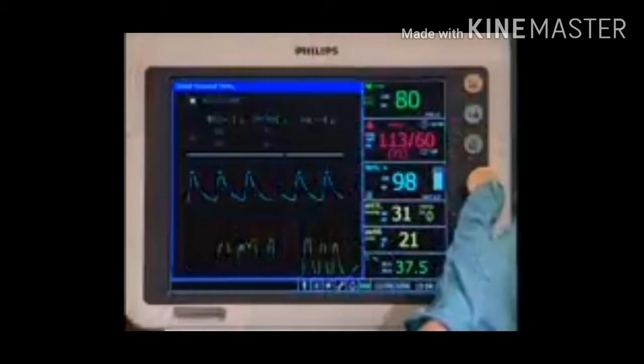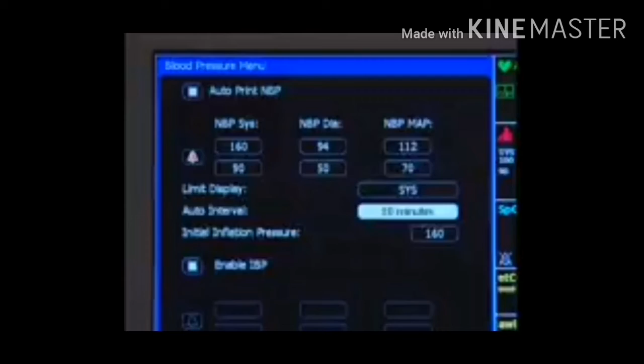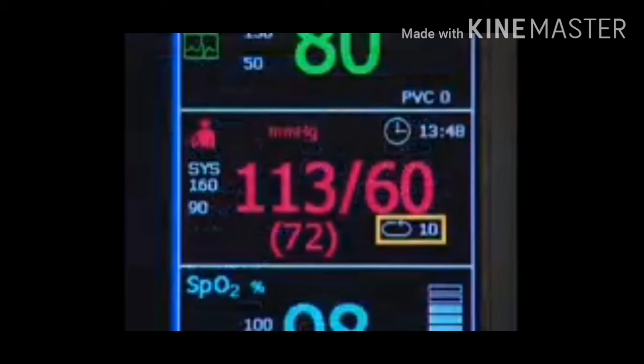There are 3 different NBP modes: manual, automatic, and stat. To change the measurement mode, highlight and select the NBP numeric pane. Choose the desired interval time. The blood pressure measurement interval displays here on the screen. Use the NBP menu to make other adjustments, such as initial inflation pressure or alarm limits. On some models, you can also use this menu to enable invasive blood pressure monitoring.